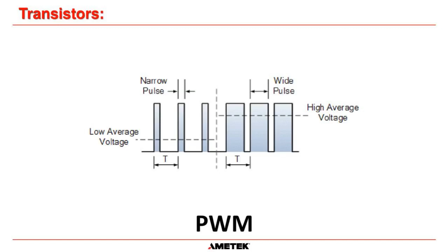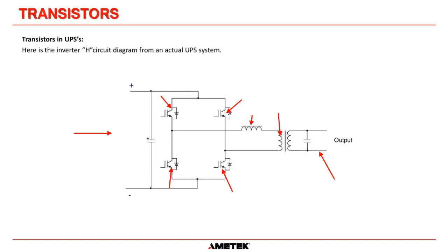Here is your input, your DC bus inside the UPS, 135 volts DC for a 60 cell system. We have one IGBT there, one there, one there, and one there. That goes through an inductor and a transformer, and then out to the load circuits.